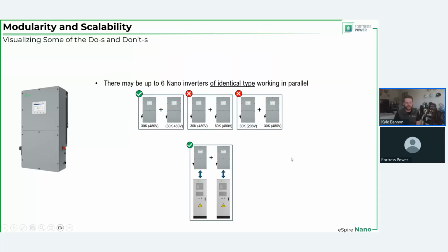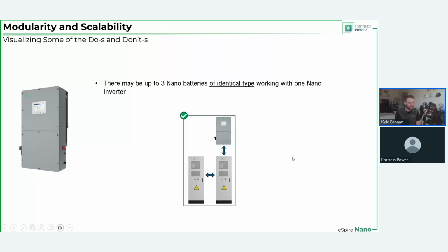Just some specifics here. This is getting a little bit into the specifics of design and how we couple these things, but I think it's important we touch on them. You can get up to 6 nano inverters of identical type working in parallel. So if you wanted to do 6 of those 30Ks or 6 of the 60Ks, I mean, 360 kW of 480 volt power, that's a ton of power. You can still do it, but you can't mix and match 30 and 60K. You can't mix and match 480 volt and 208 volt. Just keep that in mind when we're talking about sizing these things.